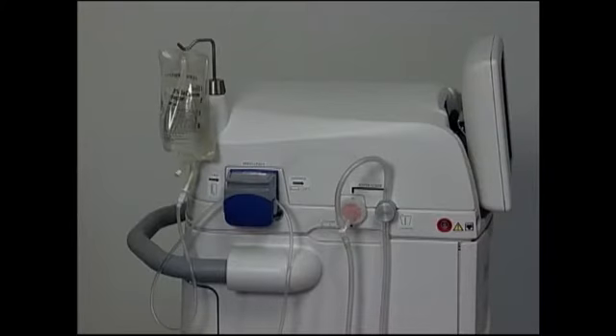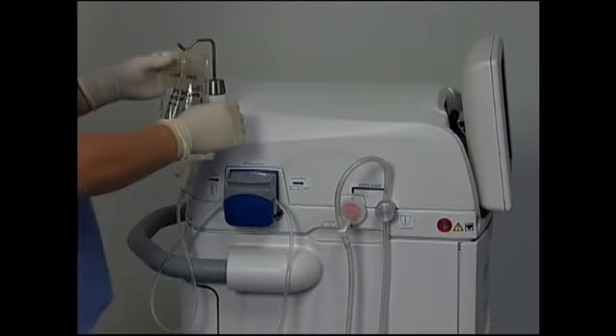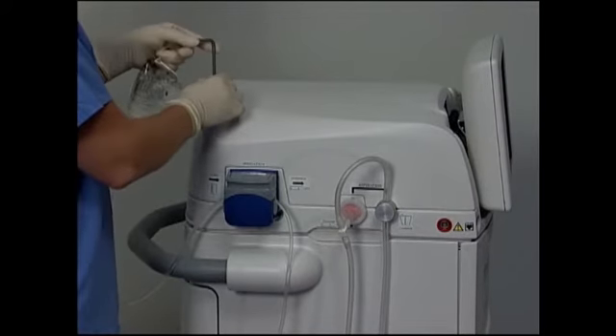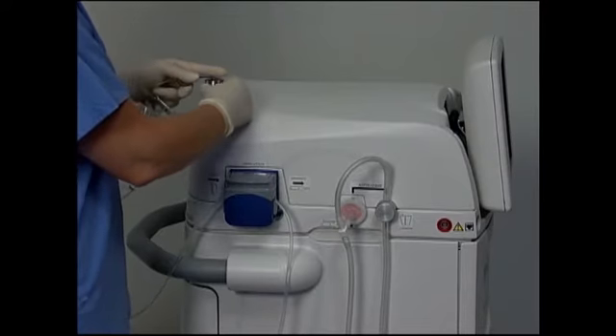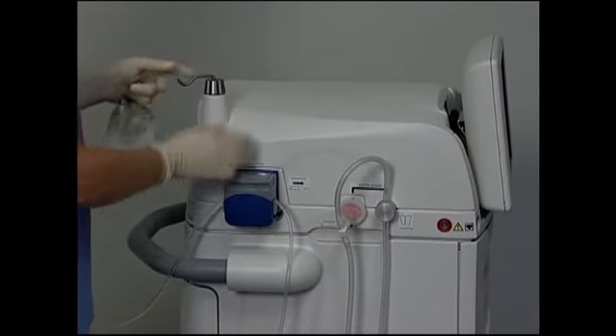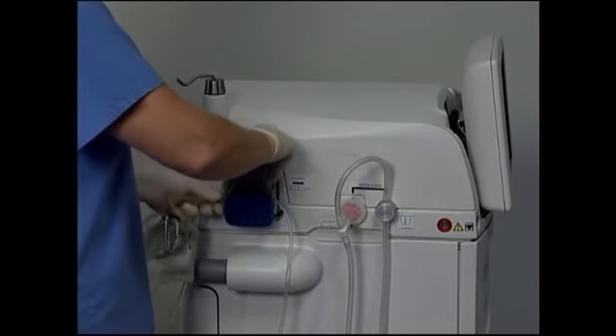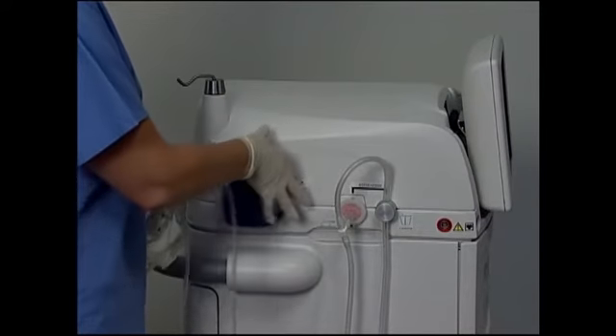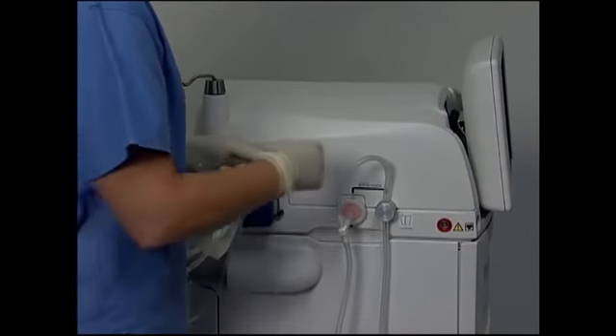Disconnect the handpiece from the console. Remove the IV bag and twist the knurled ring to store the irrigation pole. Open the peristaltic pump latch. Remove the irrigation tubing, retaining the IV bag in one hand, and close the peristaltic pump latch.